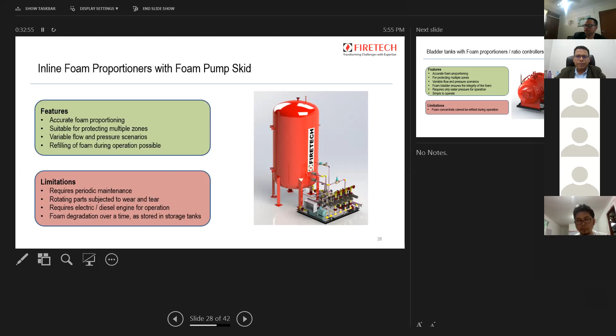Now, bladder tanks with foam proportioners and ratio controllers. Globally, this is one of the most reliable and accurate foam proportioning systems used for multiple hazards. The feature is that it is the most accurate foam proportioning system. It can protect multiple hazards by using multiple proportioners, with variable flow and variable pressure scenarios.